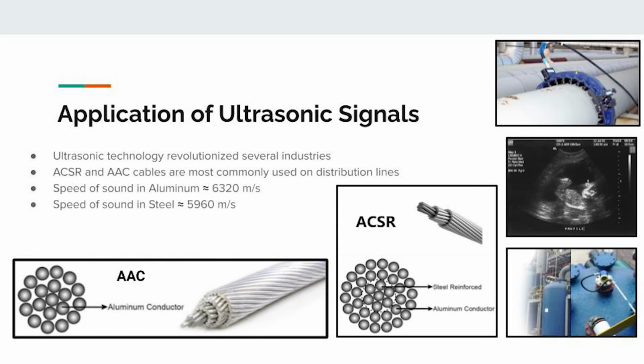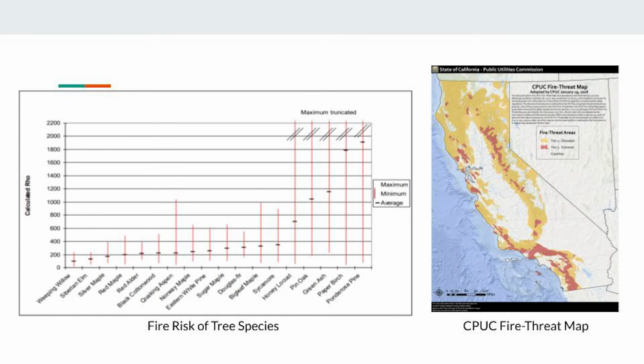damage to the line. The California Public Utility Commission estimates that about 10% of wildfires are caused by power lines. In most cases, the power line fault is caused by a nearby tree or branch coming into contact with the line. According to a 2017 study, the majority of tree conductor contacts result in high impedance faults of low current, meaning that modern overcurrent relays may not detect a lot of these faults. According to the study, there are 4 species of trees that pose a high risk of faulting.